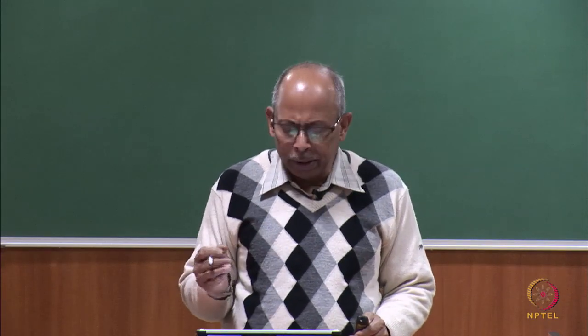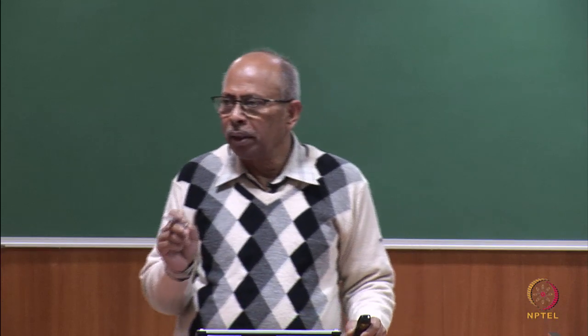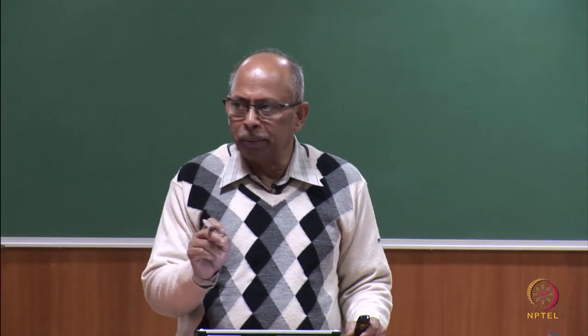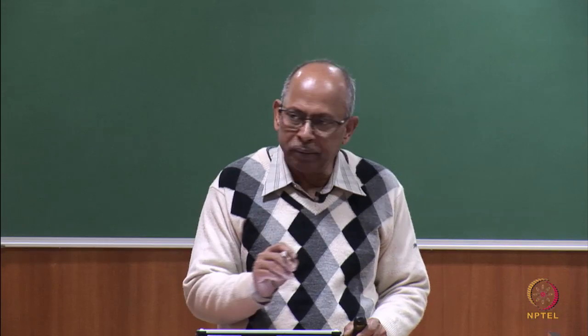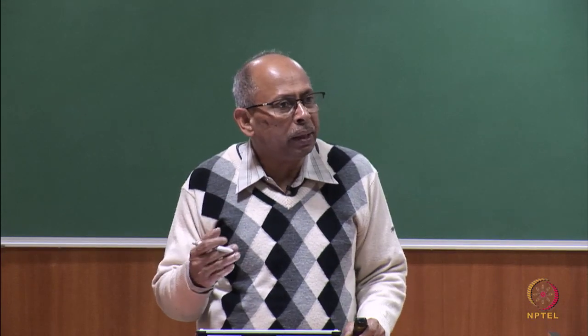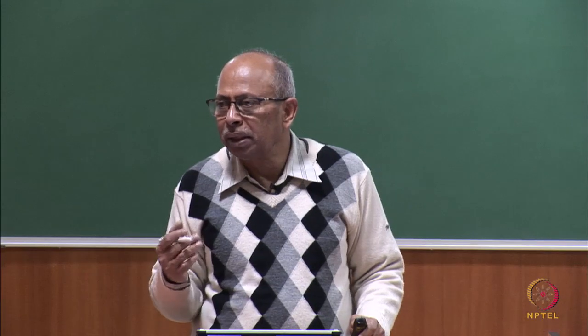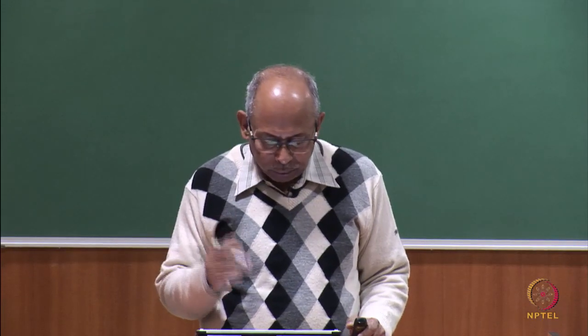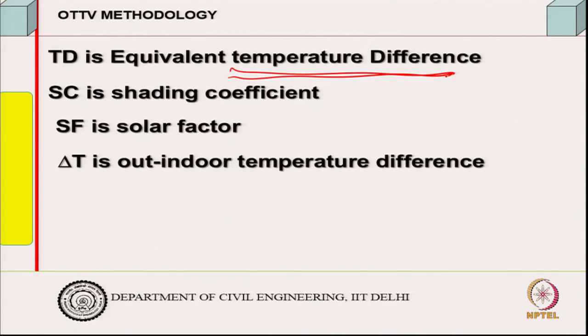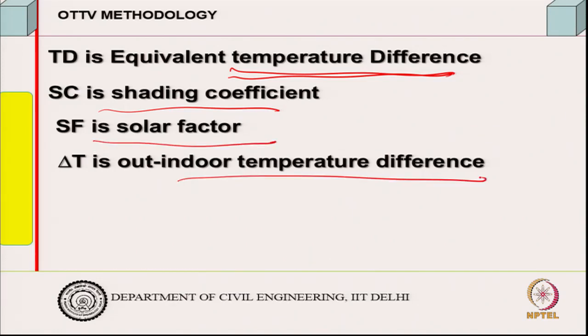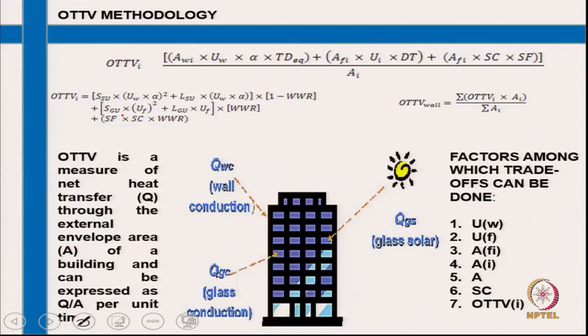For a small country like Hong Kong, it is not very difficult, they can specify a temperature difference, or Singapore can specify the temperature difference. But for Indian scenario, it has to be done for a number of cities and different climatic zones. So equivalent temperature difference, SC is the shading coefficient, this is the solar factor and the outdoor temperature difference. These values are given, and one can generate them.